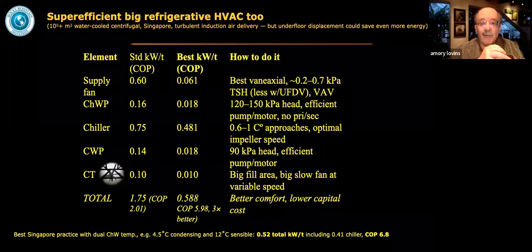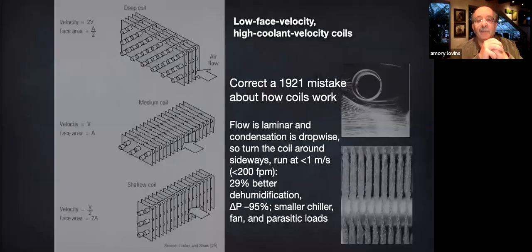So notice again the order of magnitude savings in the supply fan, the pumping loops, both of them, and the cooling tower by redesigning components, including pipes and ducts, to minimize friction and optimize performance. Now, there is one trick in Mr. Lee's whole system design, and that's rethinking the cooling coils by correcting a 1921 misinterpretation that Willis Carrier made in his lab data. Mr. Carrier thought that airflow through a cooling coil was turbulent and water condensed in a film. But the late engineering professor Sam Luxton in Adelaide found experimentally, look at the photos on the right, that actually the airflow is laminar and the condensation is dropwise.